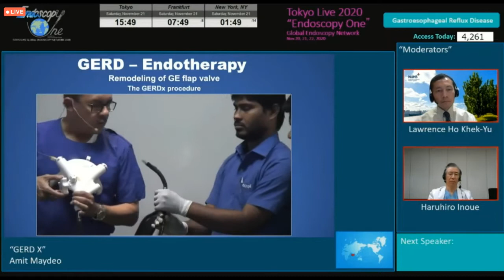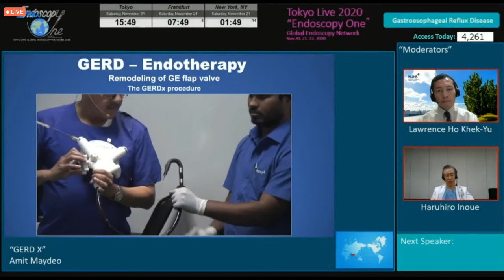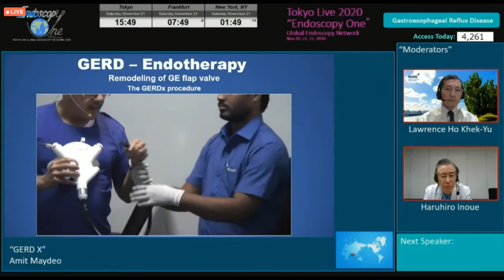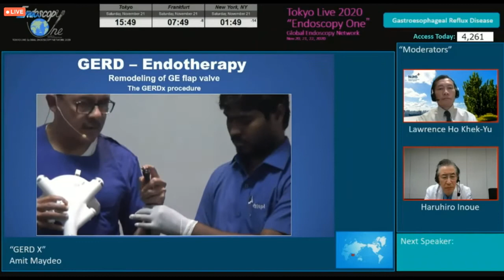You can see this big wheel and the small wheel. By rotating the big wheel in upward direction similar to an endoscope, we can turn the tip of the GERDx device in a complete U-turn so that the tip can be brought towards the LES. At the end of the GERDx device, there are these two metallic arms on which we can actually fit the disposable staple.